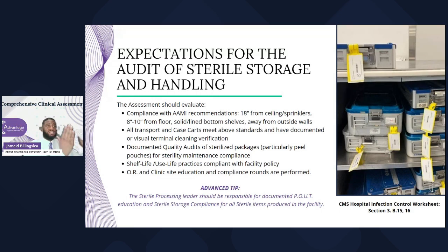How do I know they're being stored properly? How do I know that the temp and humidity is being monitored properly? How do I know they're being handled? If I'm getting point of use treatment that's not adequate, how can we hold that team responsible when we didn't deliver in services? So this is a part of our responsibility, not just in the department that we call sterile processing, but anywhere that sterile goods are stored.